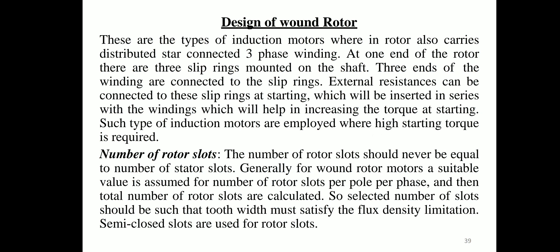In wound rotor induction motors, the rotor also carries distributed star-connected three-phase windings. At one end of the rotor, three slip rings are mounted on the shaft. The three ends of the winding are connected to the slip rings, and external resistances can be connected to these slip rings at starting, inserted in series with the windings to increase starting torque.